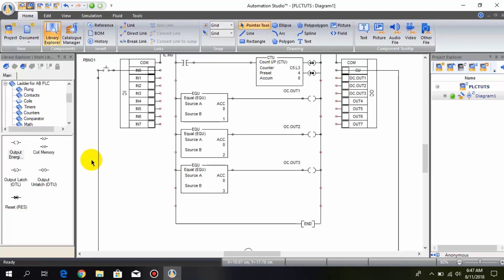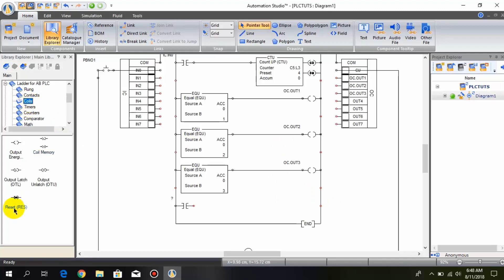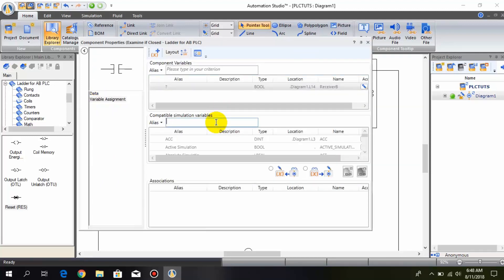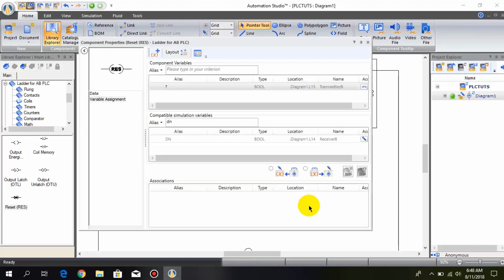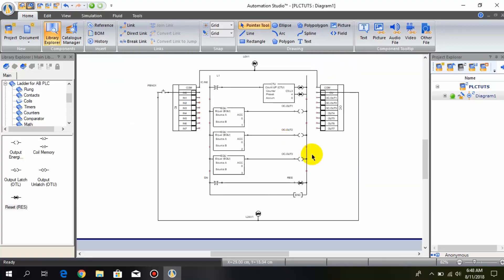Now we need a normally open contact. When the counter counts 4, the DN bit turns on, which activates this normally open contact and resets the counter again. So I connect this normally open contact with the DN bit, add a reset coil, and configure it to reset the counter. Now we are done, let's simulate.